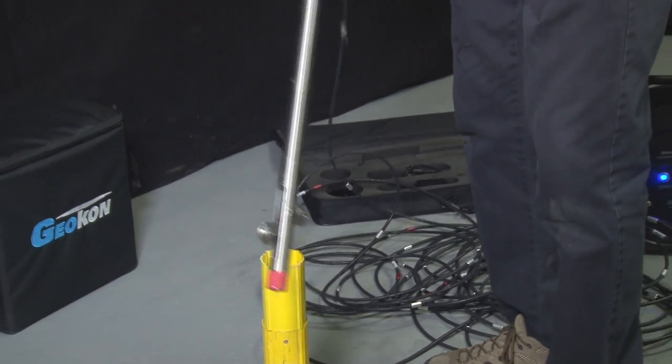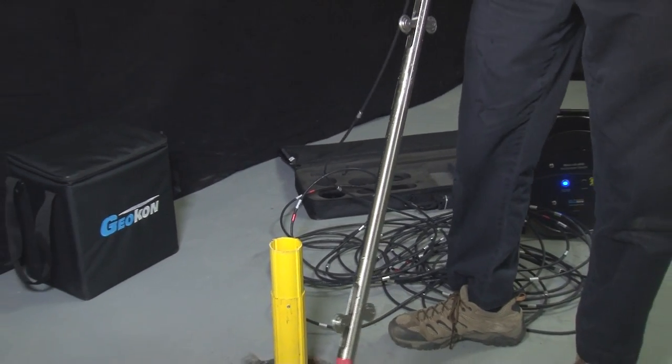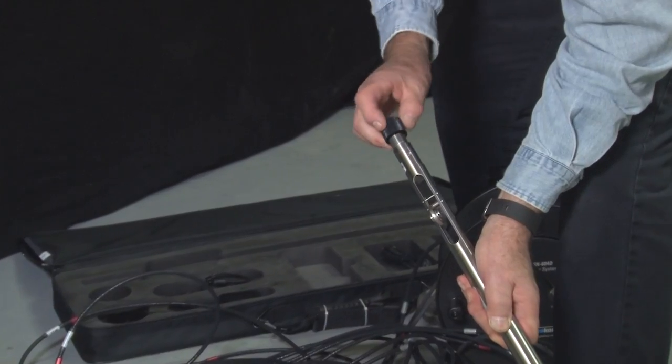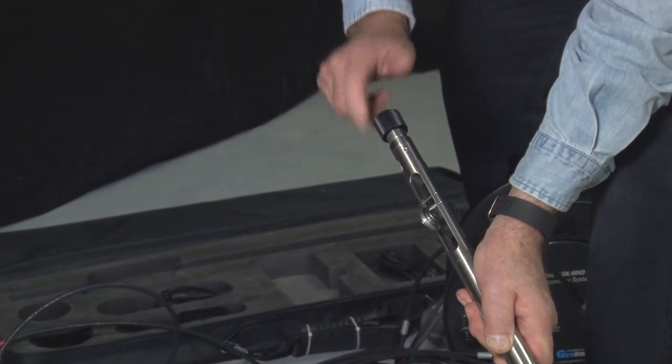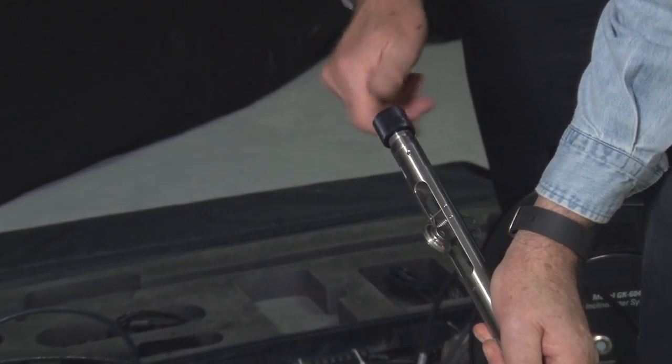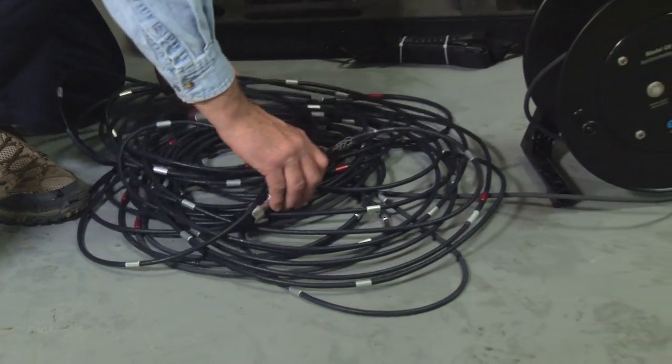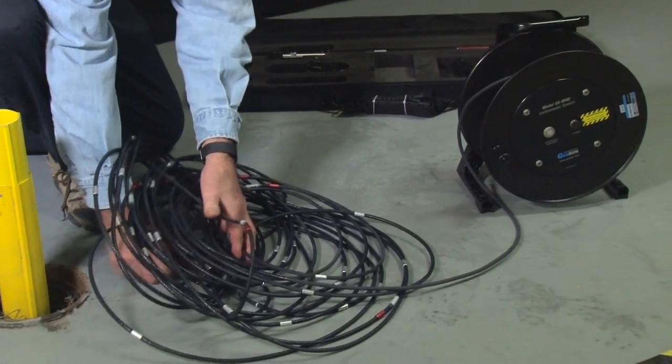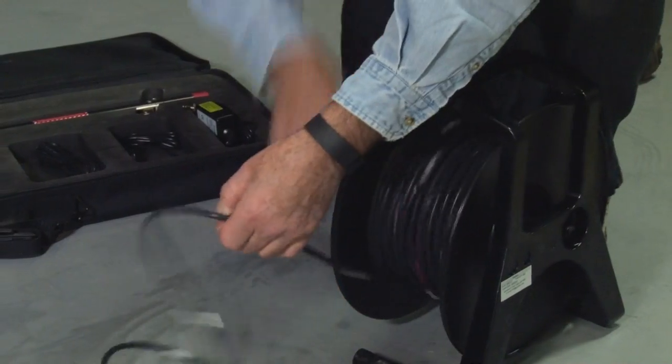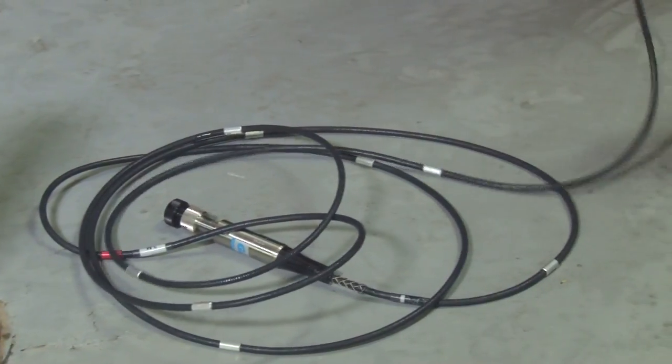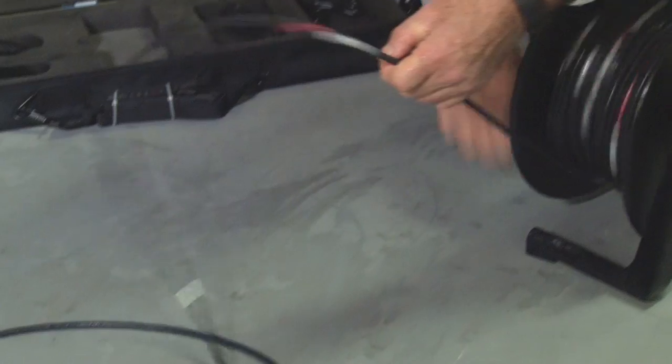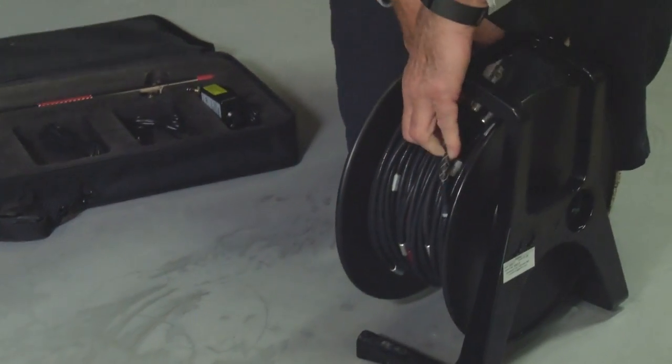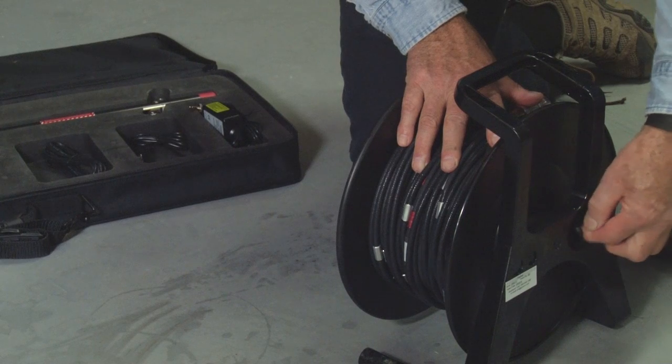Retrieve the probe from the casing. Dry it off and disconnect the probe from the control cable. Make sure to replace the probe and the cable's protective caps. Flip the pile of control cable over in order to reel in the cable without kinks. Make sure to lock the reel.